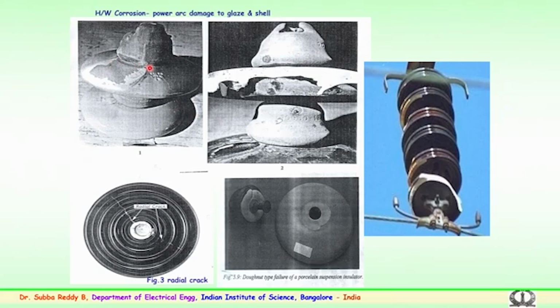You can see the glazing on the insulators over a period of time is completely not available, which will lead to surface flashover and insulator failure. This is the puncture of the insulator or breakage of the shed because of the long period of service. Similarly, because of the Portland cement, cement growth near the pin junction has led to radial cracks, or this may be because of the compressive loads the insulator has seen.